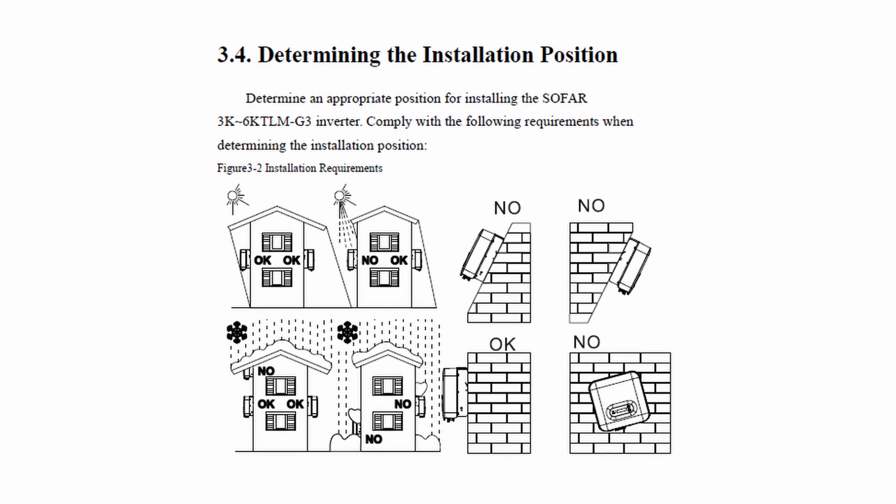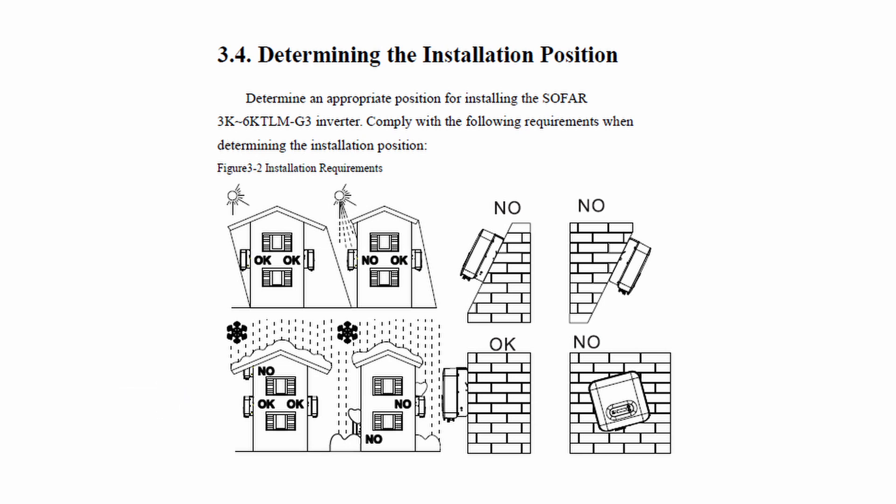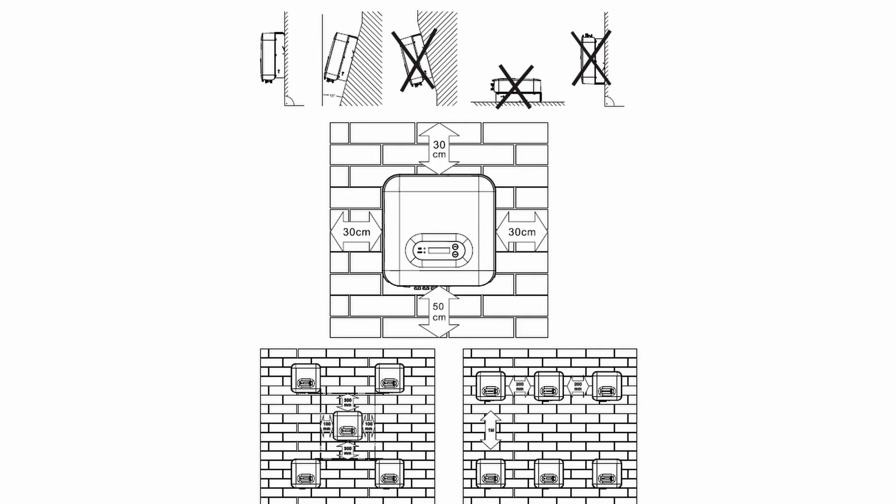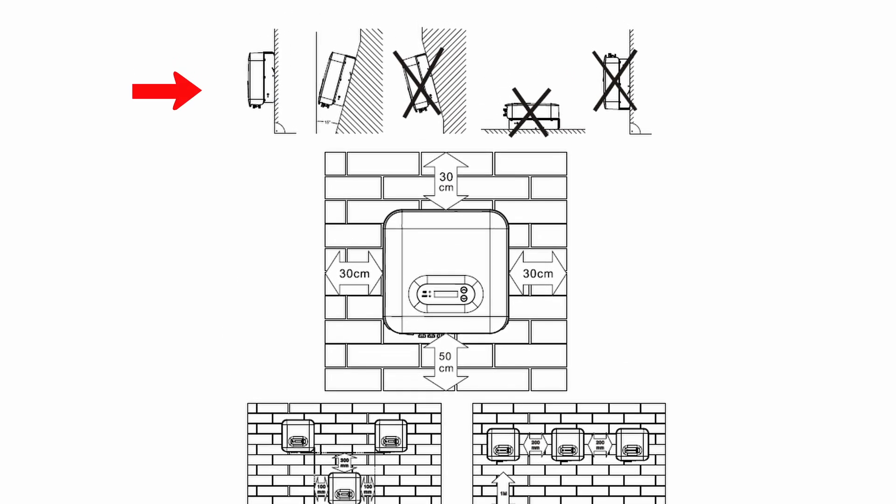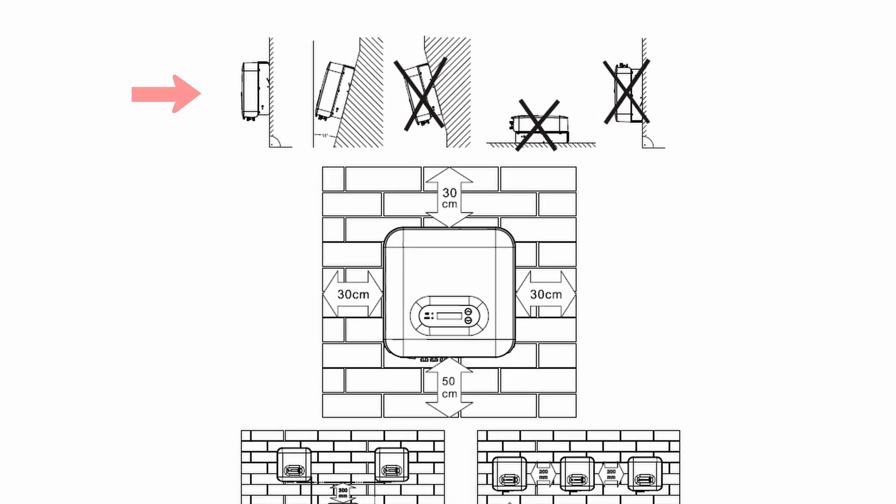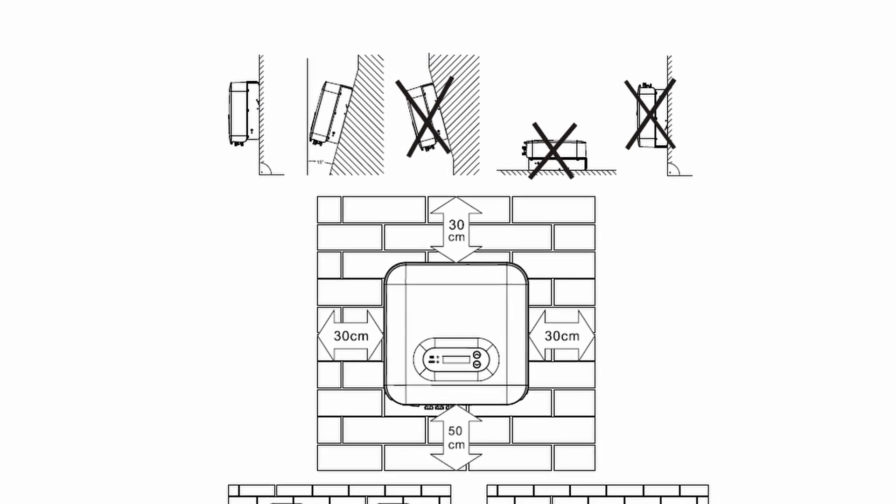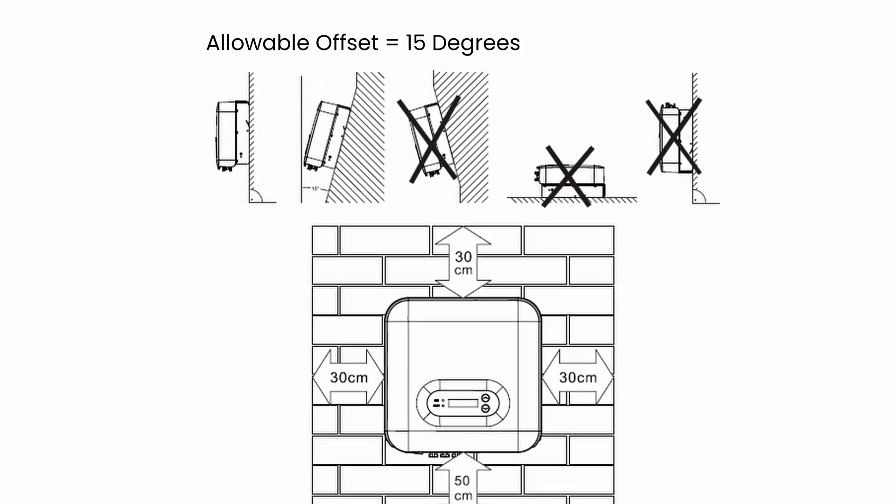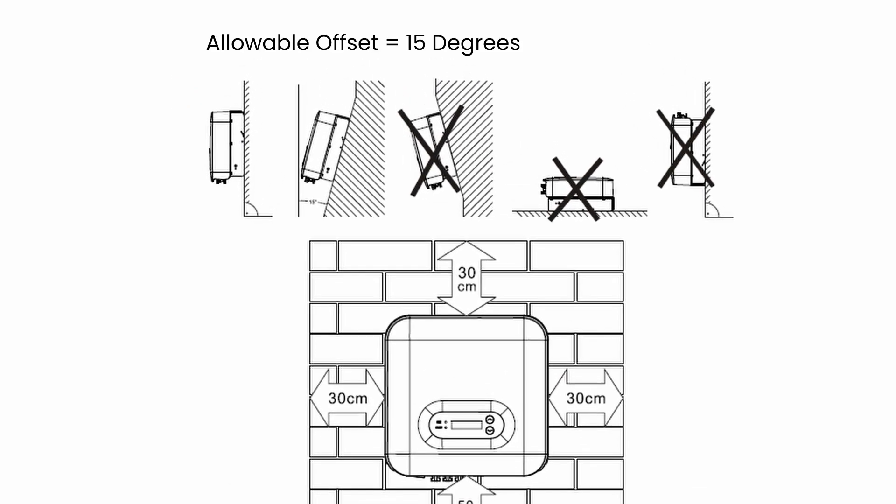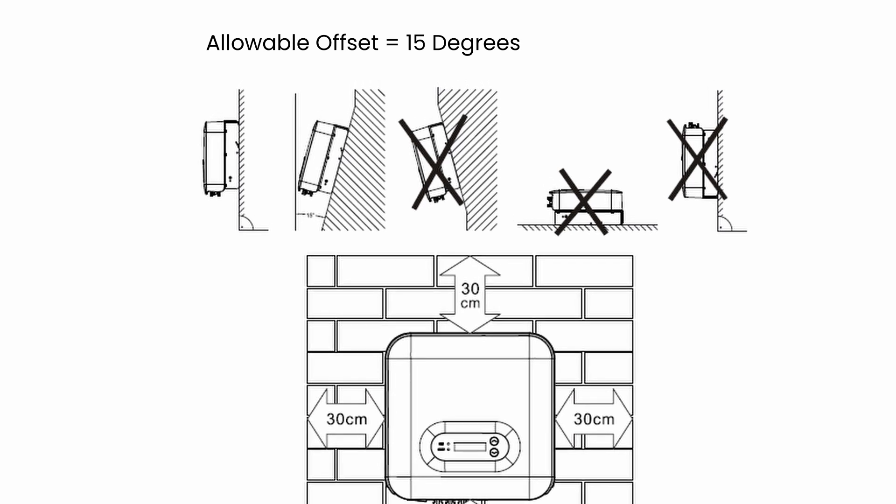Prepare the tools. The inverter placement needs to be covered by some means - don't leave it in direct weather conditions as this will shorten the lifespan. Don't place it under odd angles or let it be covered by snow or direct weather conditions. Make sure the inverter is fitted vertically on the wall with allowable offset of 15 degrees.